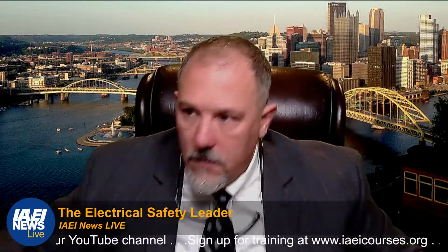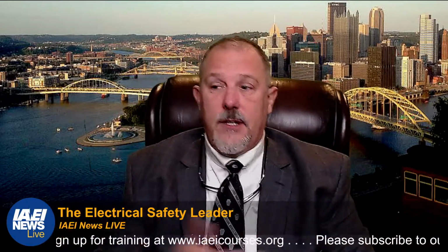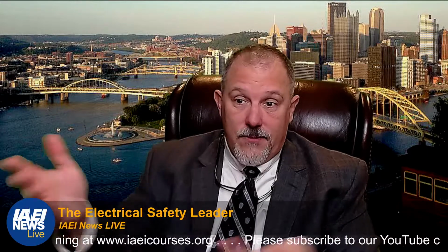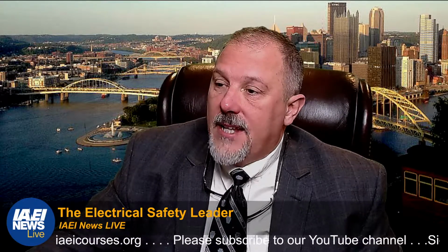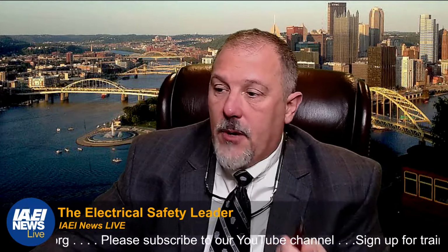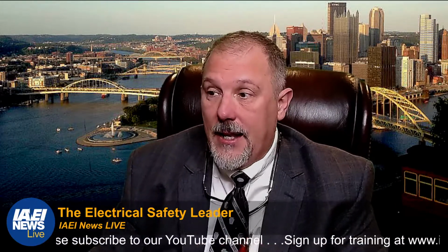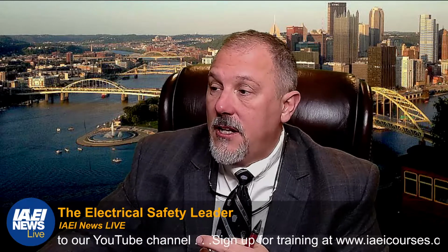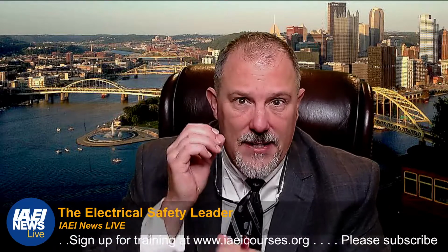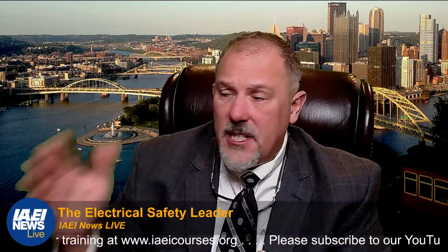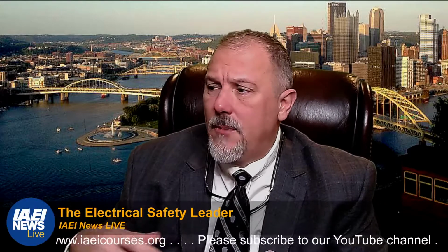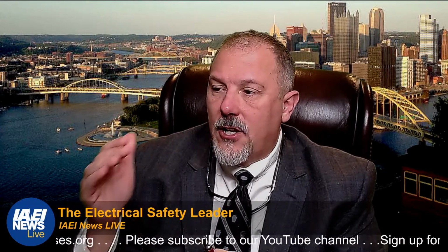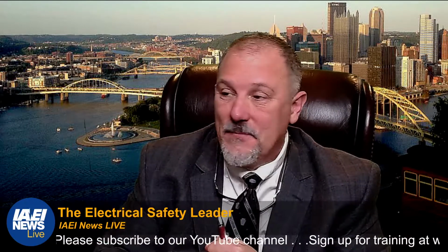All right, let's go back. I'm going to look at Circuit Breakers, Chapter 15, just because that's where I'm at. So 70B, visual inspection of circuit breakers. They have a table on cleaning electrical equipment, services, and enclosures: insulating materials shall be kept clean and contaminant-free. They tell you that if contamination is found, such as the presence of dust or moisture, you clean it in accordance with Section 5.8. And 5.8, Chapter 5, covers general requirements.